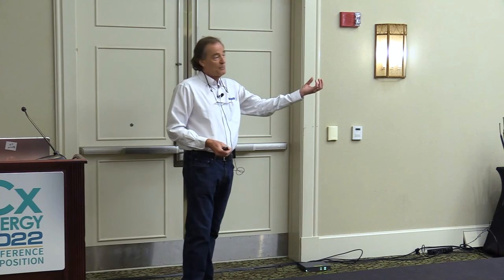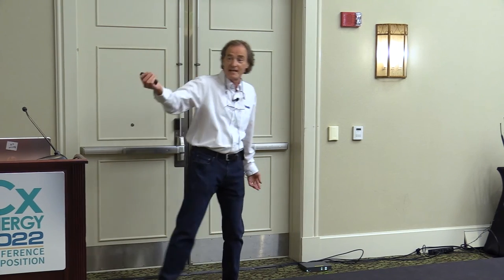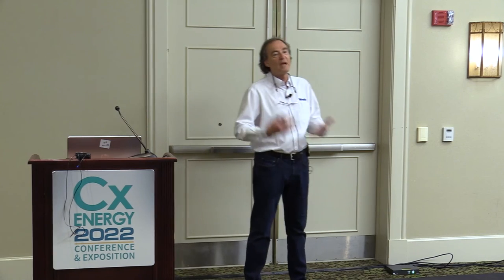Guess what? Units is metadata. It describes the data. The temperature, 76.2, is the data. The metadata is the units. Well, that's a simple example, but let's go further. What's it measuring? Air. In what? Room 7. Served by which AHU? AHU 2. On what schedule? Occupancy schedule 5. That's metadata. Well, what Haystack does is provide a standard way to represent that.